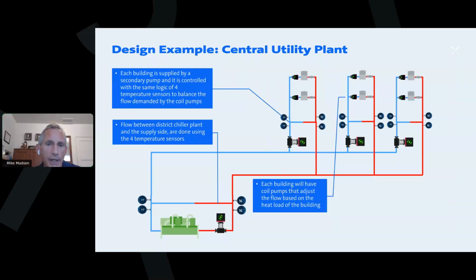But if you don't have heat exchangers, you're going to have something more like what's shown on the screen here. So here would be my primary central plant. We'd put a decoupler at the central plant, and then we're going out with a chilled water supply. And this would be an individual building 2 and individual building 3. We would have a house pump, a decoupler, and then the smart pumps on each air handler unit.